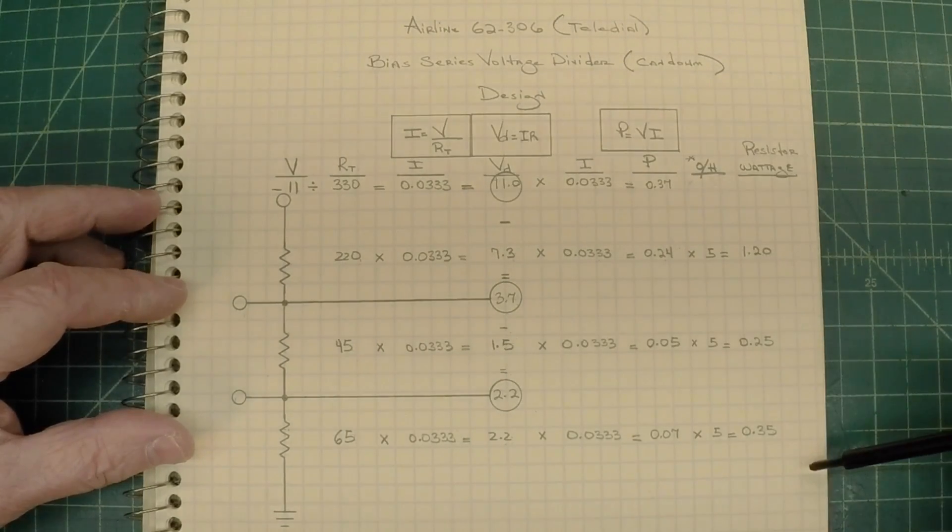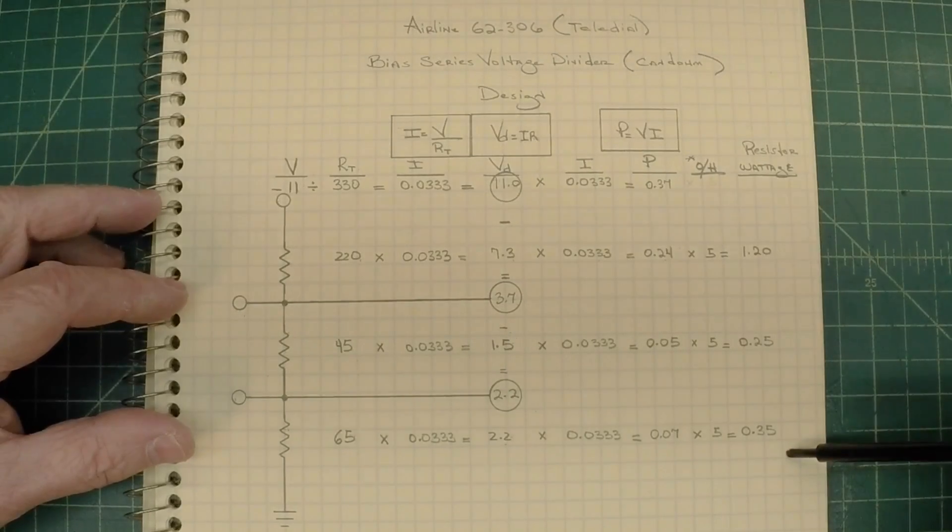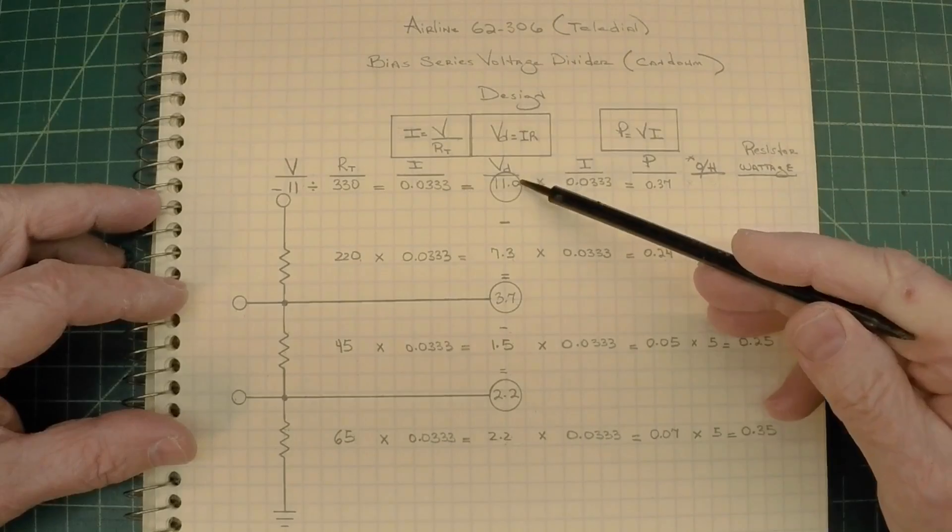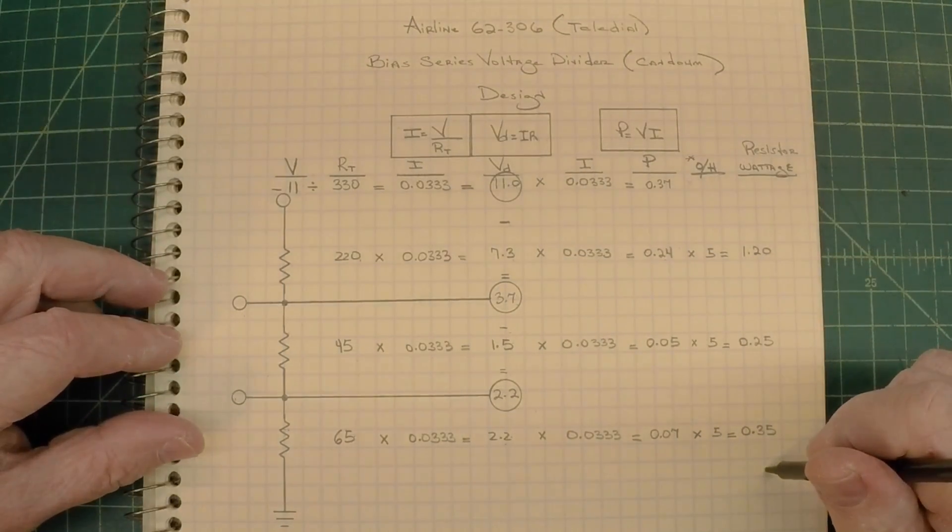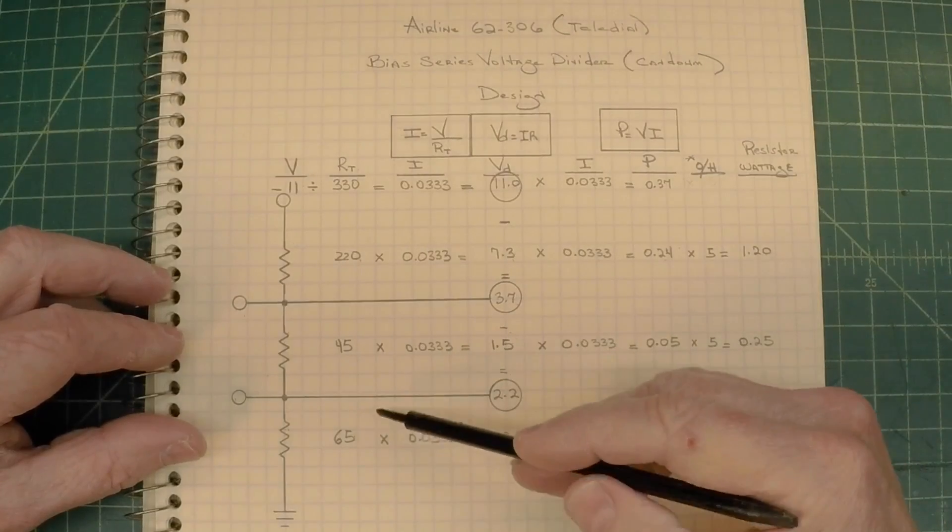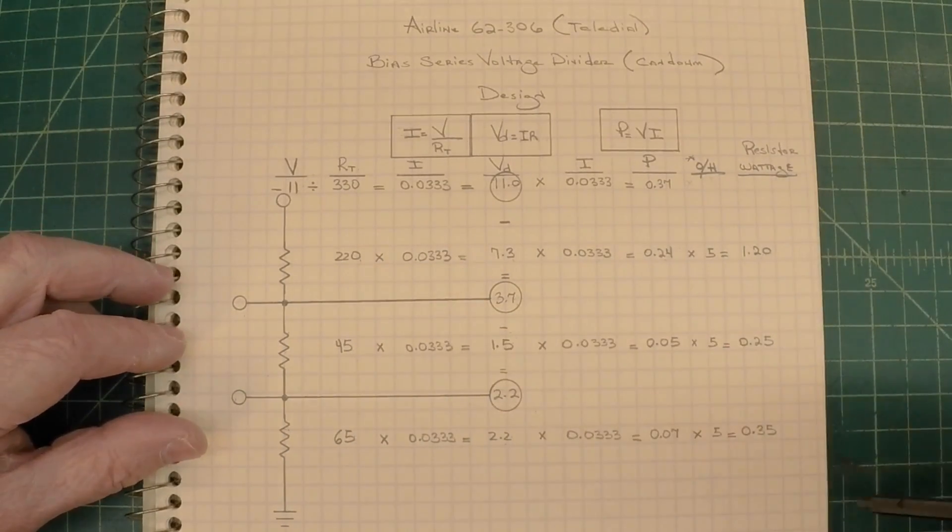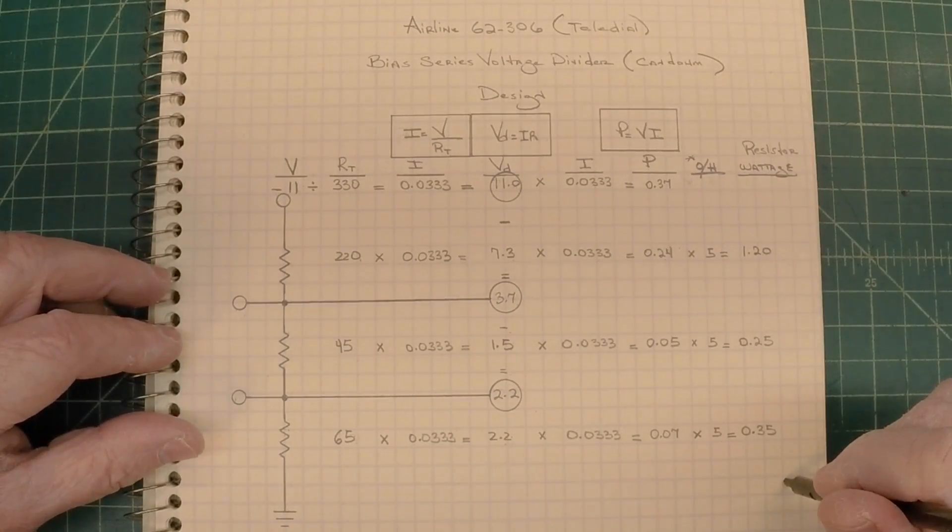So I hope that's helpful, folks. That's the basic math on how to figure things out. And you can see the numbers that we've called out here closely mirror what we had off of the Candohm testing, which those values are a little north or south of what's called out on the schematic, but still within 20% of their original design.